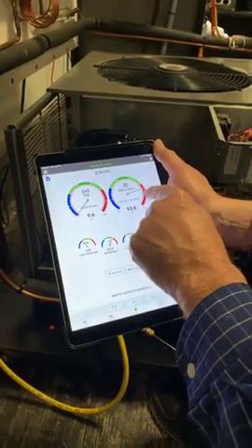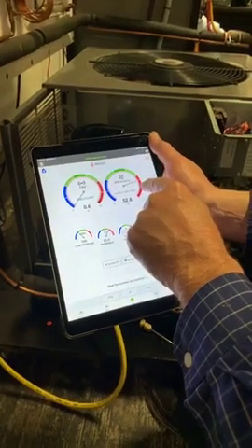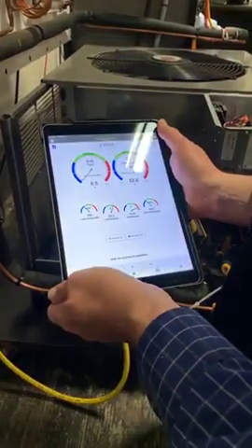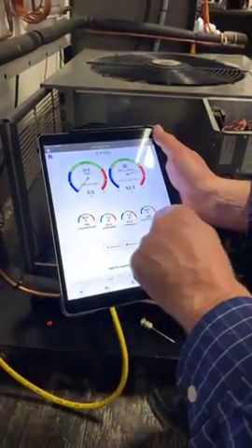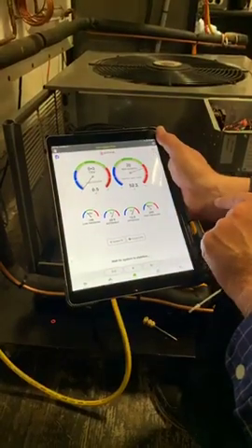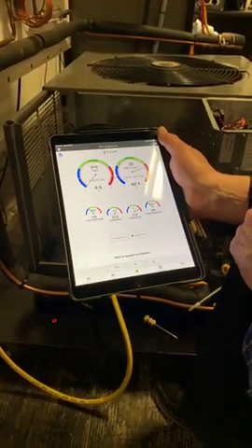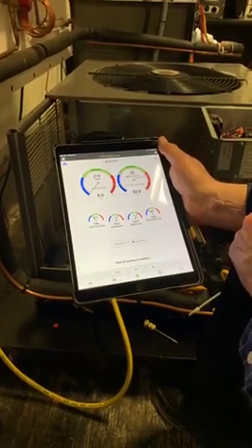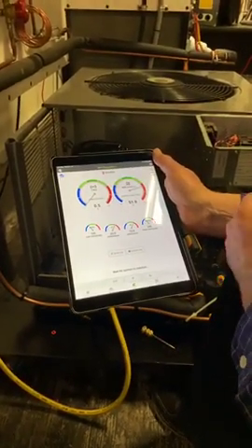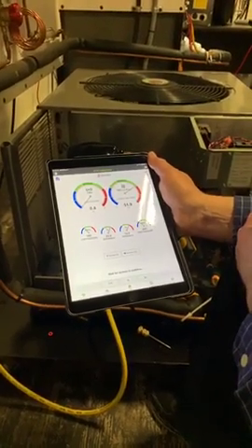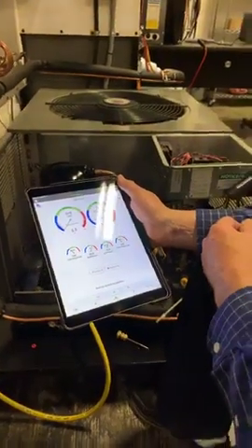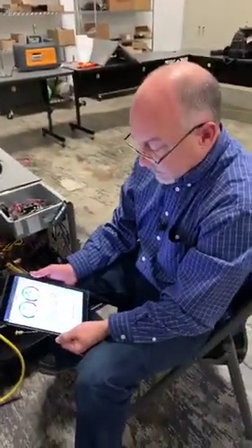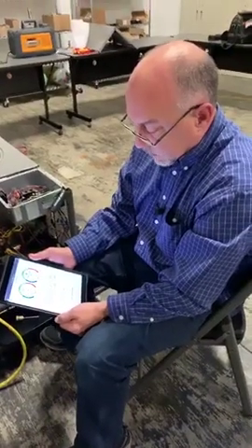We've got a low temperature split, which will probably move closer into range, so the supply temperature is too high coming out. Subcooling is really low, and our low pressure is low and our high pressure is low. All those things are indicators of low charge, but this will walk you through what our next step is. Because this is so far away from our subcooling target, it's going to tell us to add gas once it stabilizes. I apologize because it took off a little slowly and we got stuck here for a minute, but we're going to tough it out and make it all work.